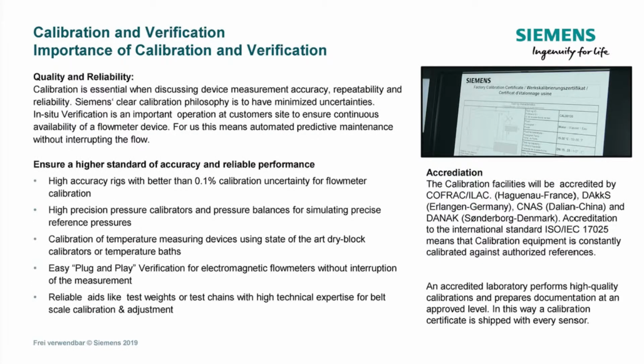The importance of calibration and verification. Calibration is essential when discussing device measurement accuracy, repeatability, and reliability. Siemens' clear calibration philosophy is to have minimized uncertainties. In situ verification is an important operation at the customer's site to ensure continuous availability of a flowmeter device. For Siemens, this means automated predictive maintenance without interrupting the flow. Ensure a higher standard of accuracy and reliable performance.